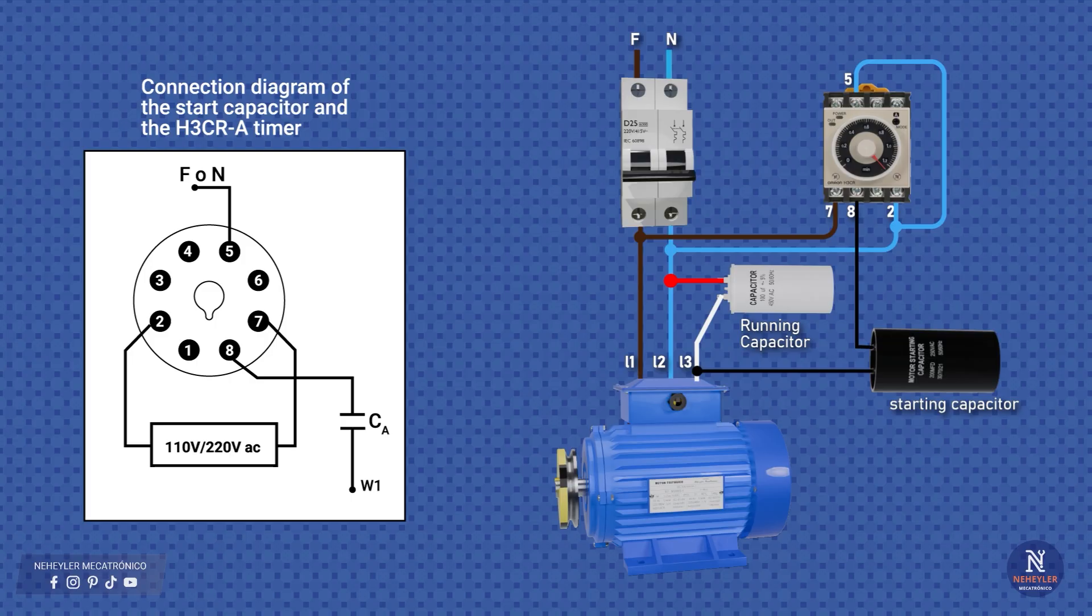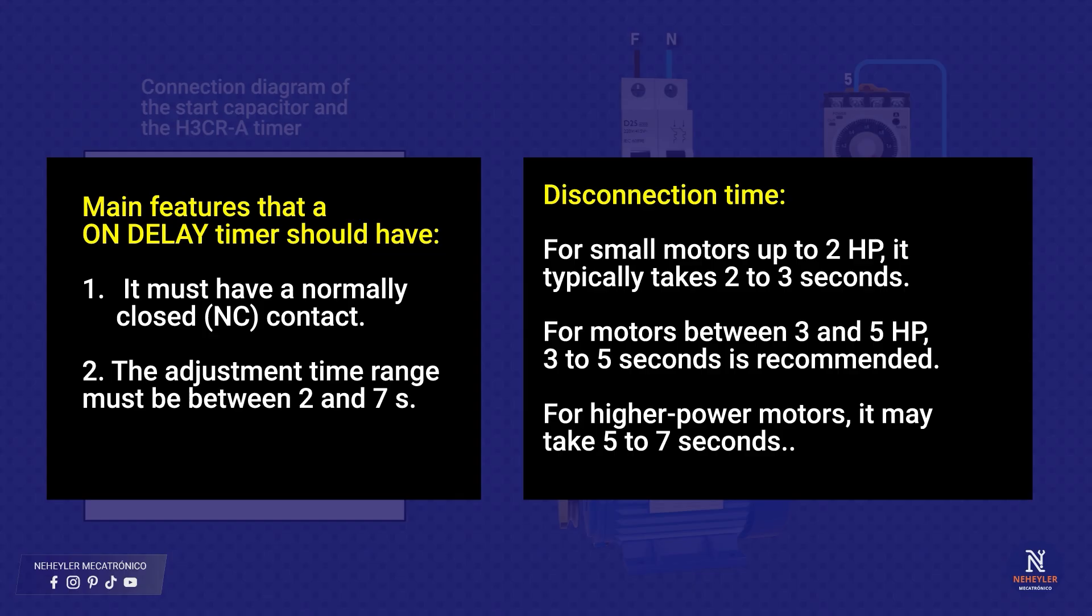Now, an important clarification, if you want to use another type of timer, you must check two main characteristics. That it has a normally closed contact, since we need it to disconnect the start capacitor, and that the adjustment time range includes between 1 and 10 seconds, which is the ideal connection time for most motors.